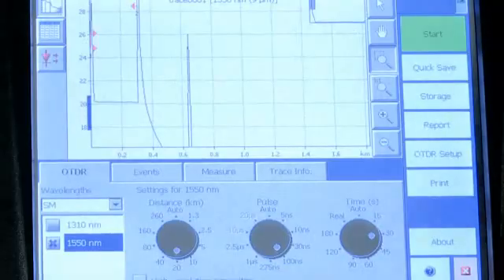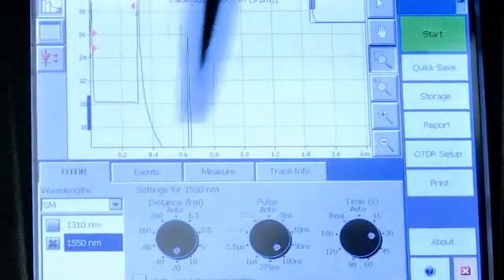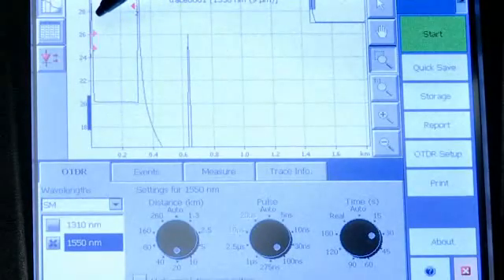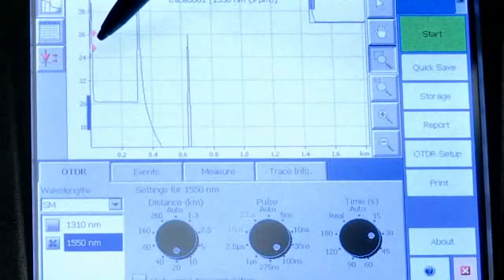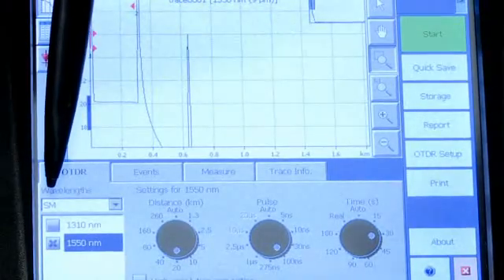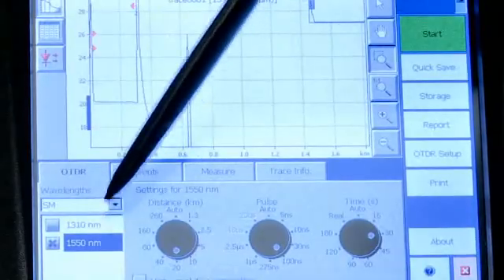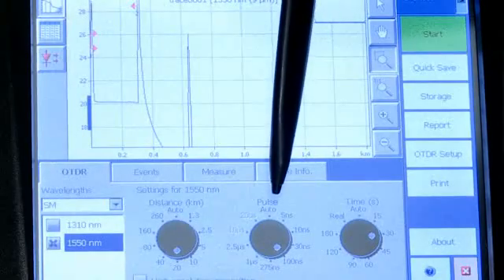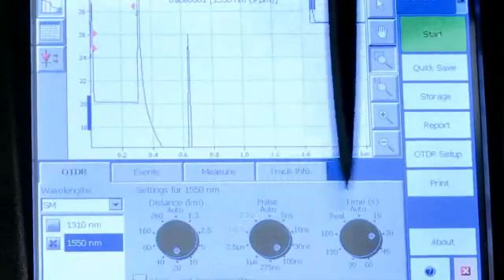A typical OTDR screen has a y-axis and an x-axis. The x-axis measures distance and the y-axis measures attenuation and reflection in units of decibels. In addition you have an ability to select the type of system you're testing. In this case it's a single mode system and the wavelengths under which to test the system. You can also select the length of the system and also the signal power which is selected by choosing various pulse widths and also you can select the acquisition time.